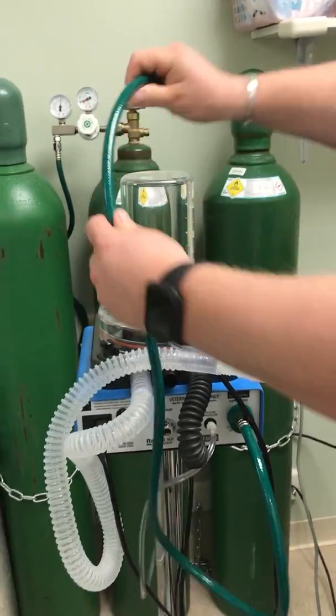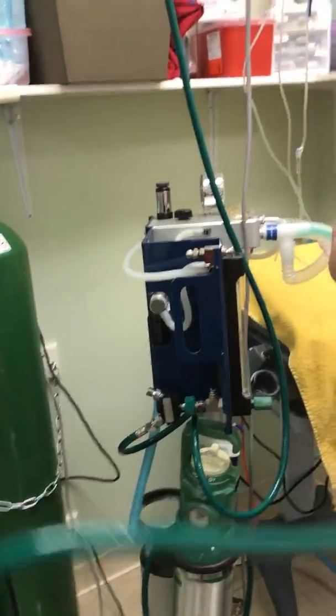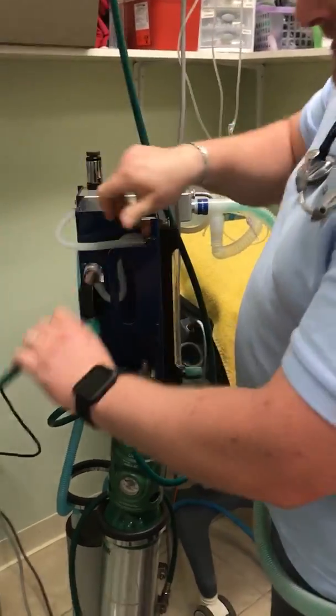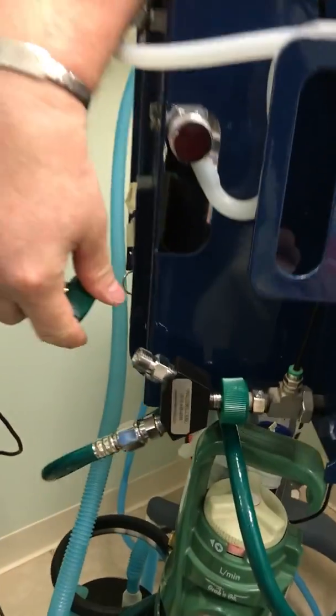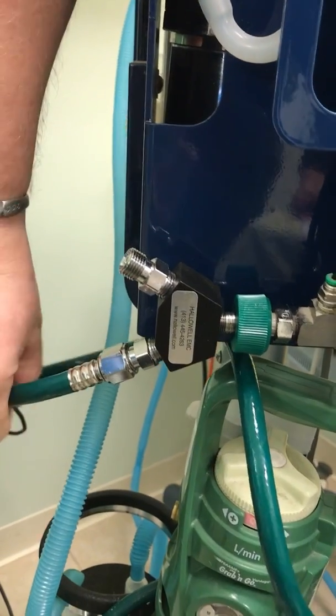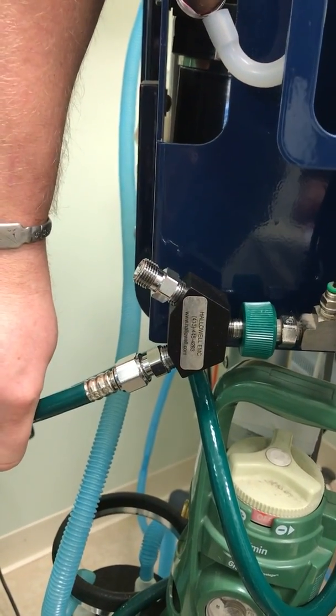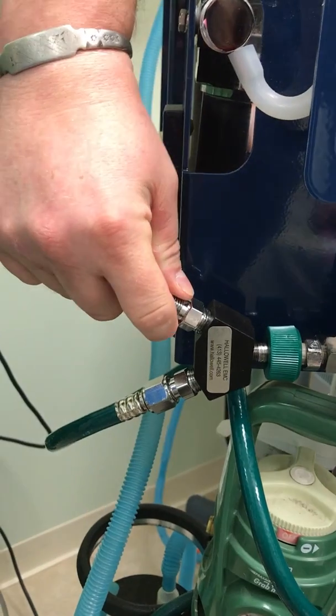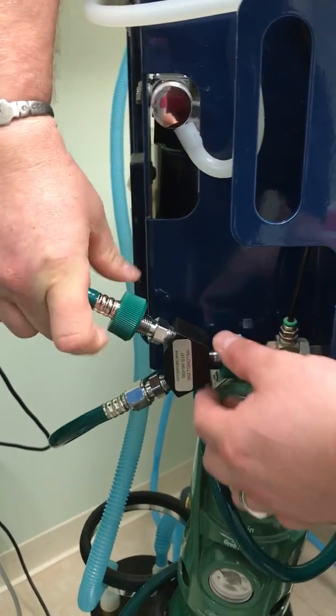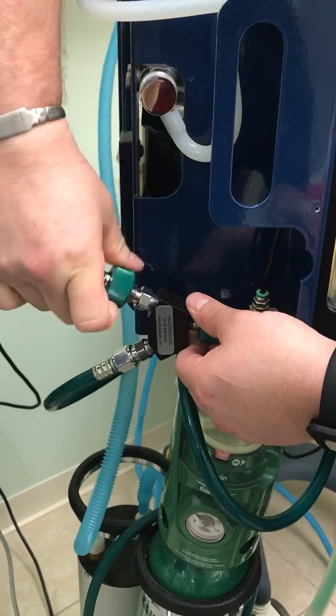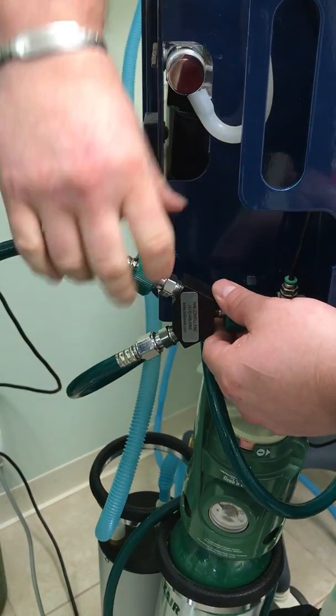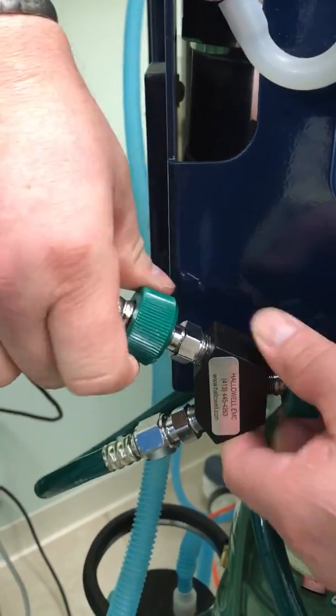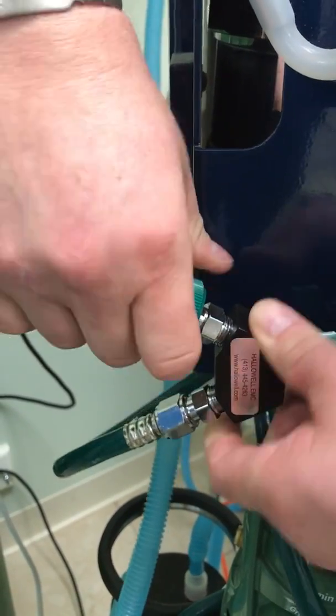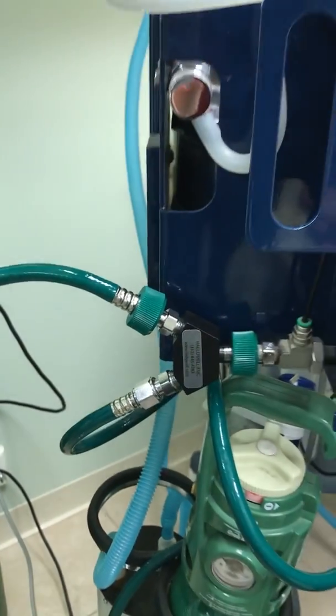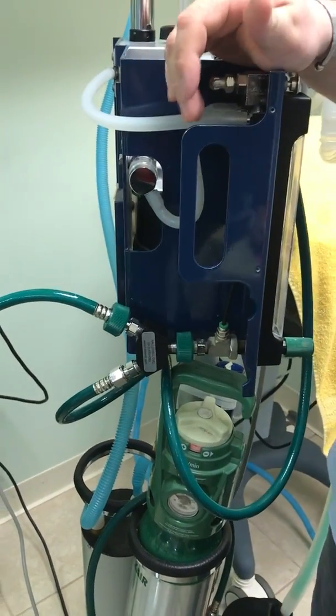The next thing you're going to do is hook up your ventilator system to oxygen. And so oxygen is always the green hose. In the back of your anesthesia machine, there is a Y piece with the incoming oxygen to the anesthesia machine and an extra valve here. So you're going to attach this hose here, and you will hear some air leakage until it's tight. And that air leakage should stop once it's fully tight. And you're just going finger tight. You don't need to crank down on it.